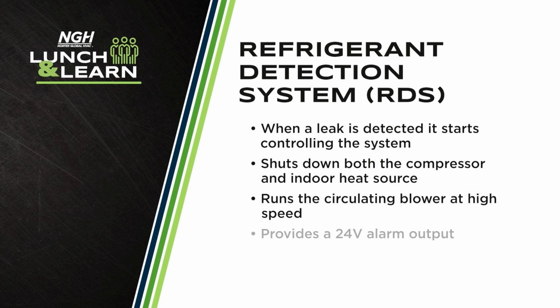The RDS also provides a 24-volt alarm output, which can be used as the details of the installation and local codes require. In most cases, the homeowner will experience a leak event as a loss of heat or cooling operation. By circulating the refrigerant throughout the conditioned space using the indoor blower, the RDS can reduce the concentration of refrigerant below the LFL. A2L refrigerants are nothing to be afraid of, but they do require some respect.